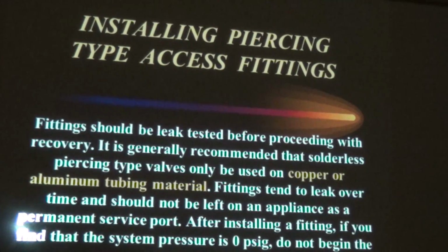Now, this is the piercing valves. This is how you're going to get in to remove the refrigerant that's in the small equipment. It's through the piercing valves. Fittings should be leak tested before proceeding with recovery. It is generally recommended that solderless piercing valves only be used on two kinds of material, copper and aluminum. These fittings will leak, and they cannot be left on there as permanent ports for removing and charging refrigerant.